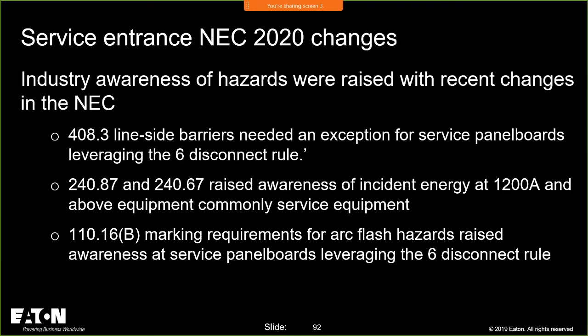WebEx. So we had a requirement in 408.3 that basically says all of the line side barriers. But what we had to do for service entrance equipment in that article, we had to say, with an exception, that if you're using the 6 disconnect rule, you don't have to do a line side barrier. And the reason was because we can't take a panel board or that meter center that's utilizing 6 disconnects and say, I'm going to put a barrier. You're going to require a barrier on it, because it's not possible.